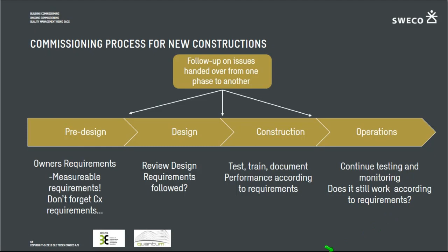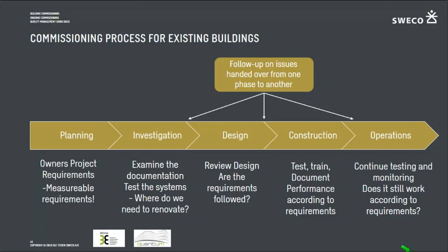If we take the commissioning process for existing buildings, it's almost the same, because you start with planning, and in the planning phase you get the owner's project requirements, the same as the other one. Then you have an investigation phase, which is what we saw in the case, where we actually examine what is there and test it. Then we review the design, since what is being renovated has to be designed, and from there on we run an ordinary commissioning process forward.